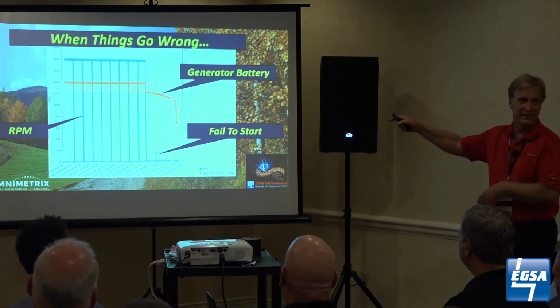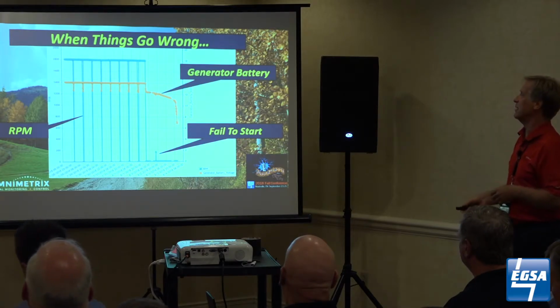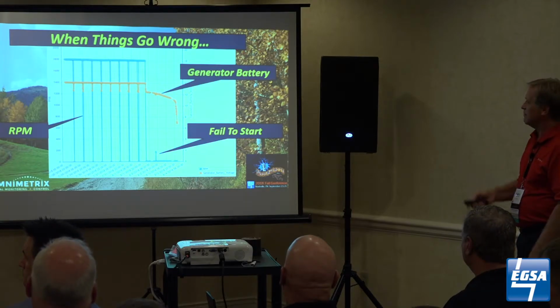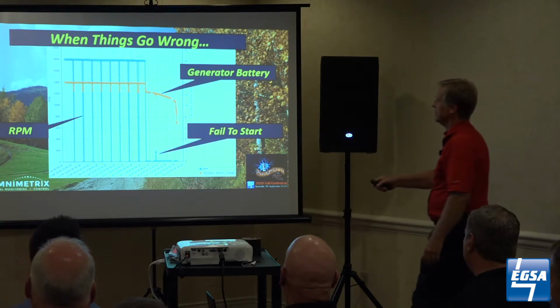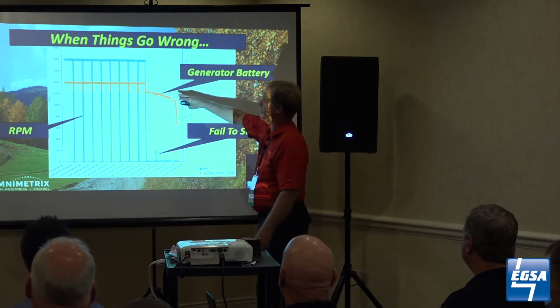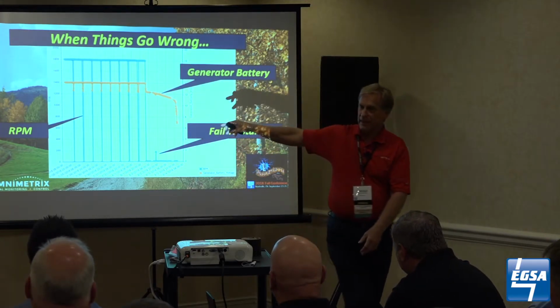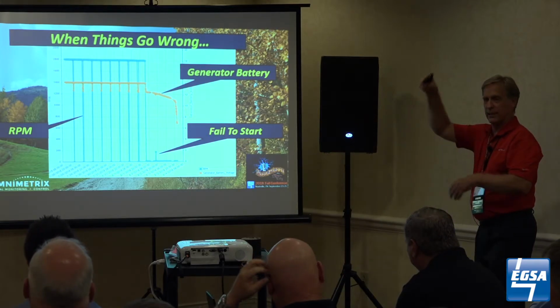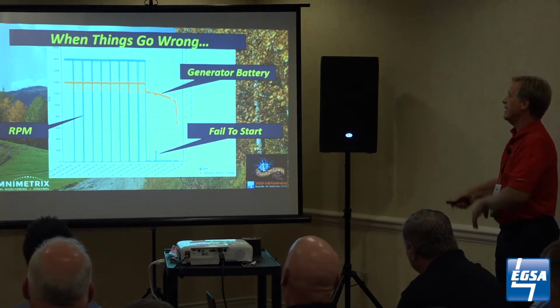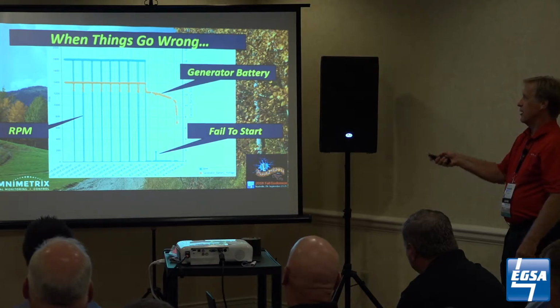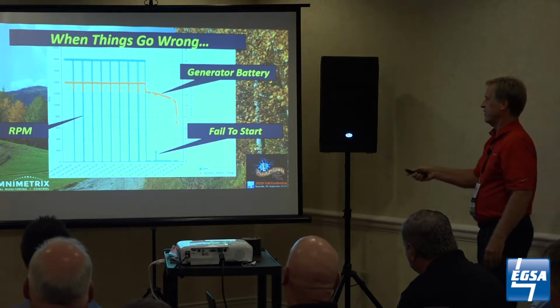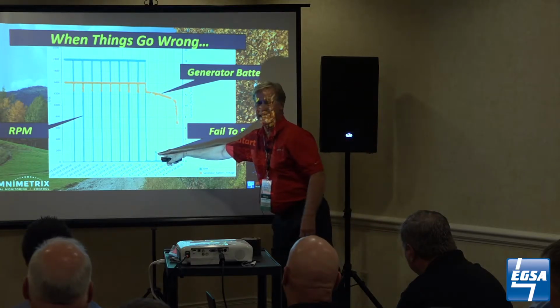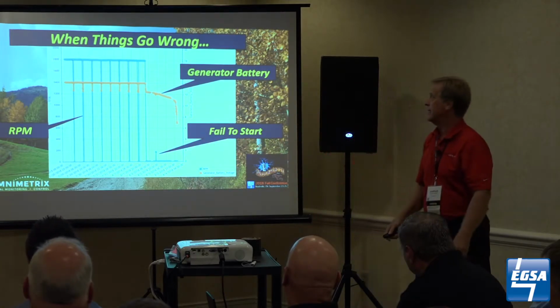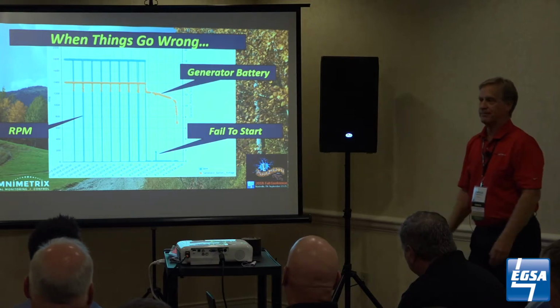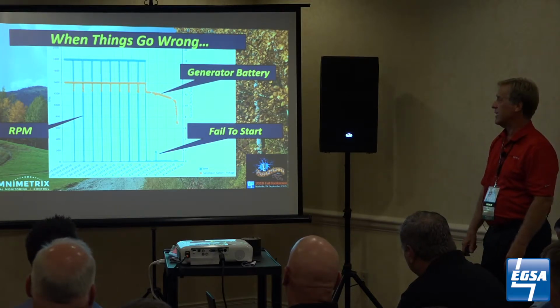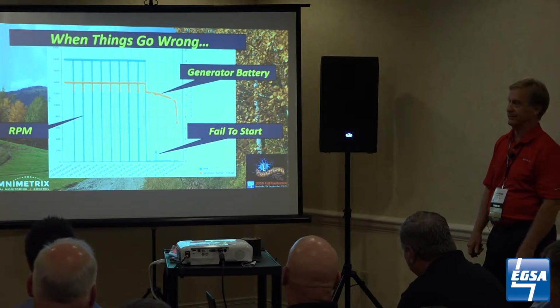Remember, we said the battery is discharging appropriately and charging properly. Well, sometimes things just don't go right. So what we see here is the genset battery in gold and RPMs in blue, showing the cycling of the gensets - on and off, charging and discharging, running and running until it doesn't. There was a fail to start right here - you can see the RPMs didn't get there, just did not light up. Once you get into a fail to start, that genset control is locked out and somebody has to go push a button physically.